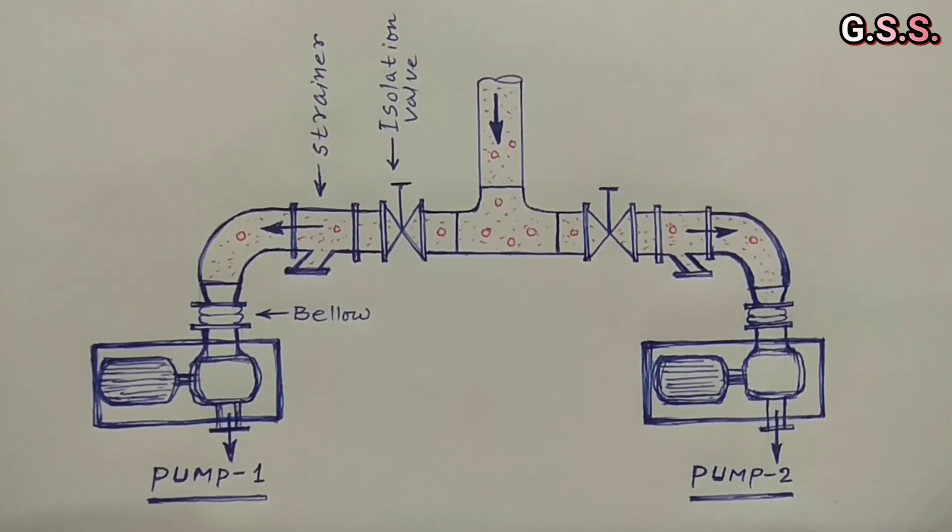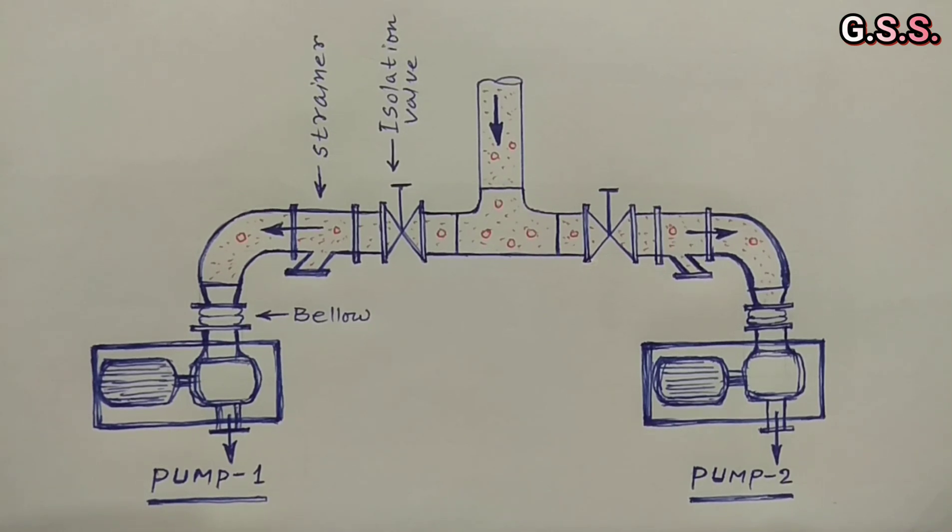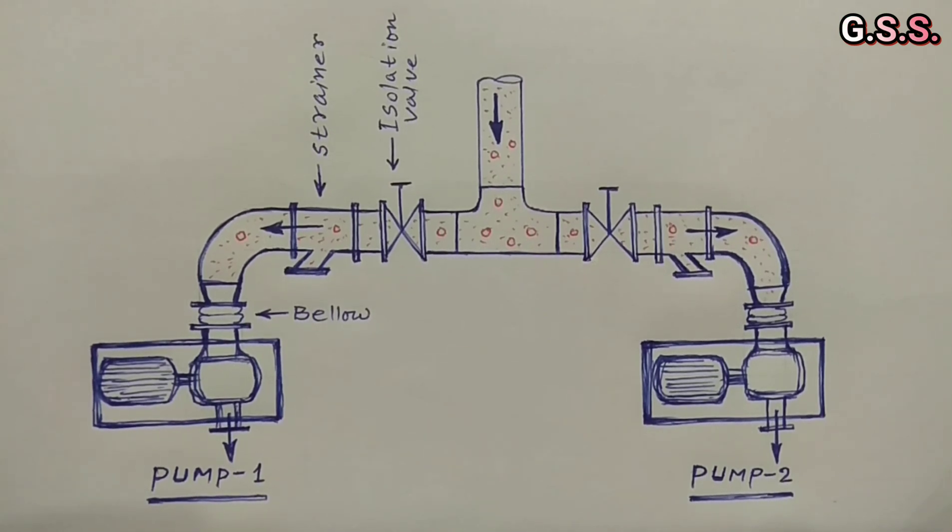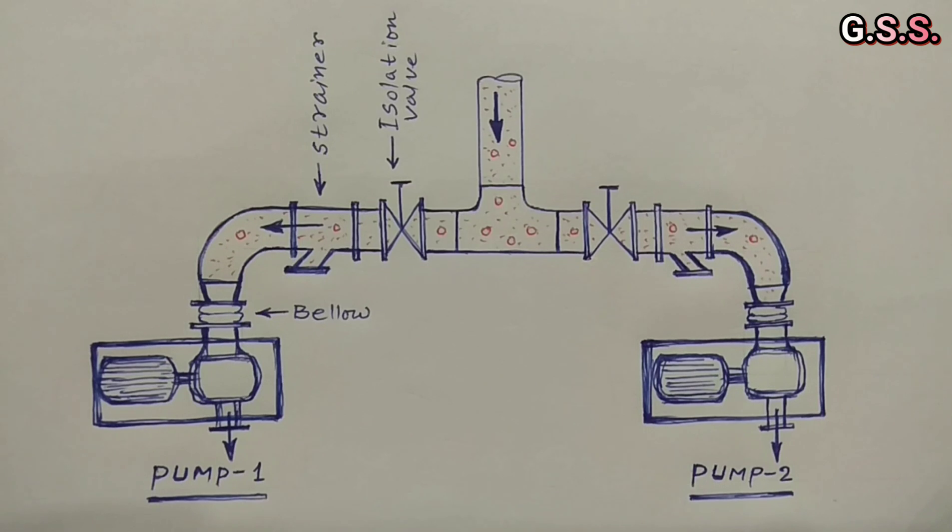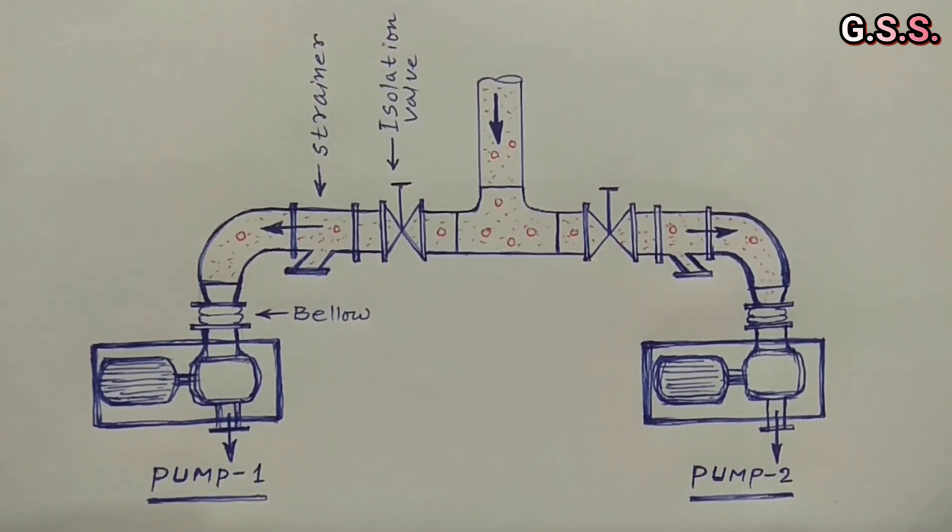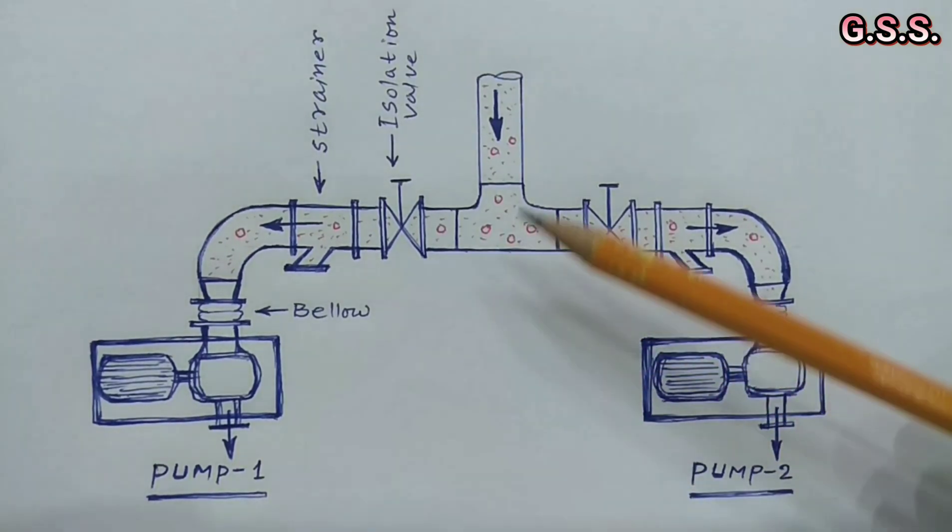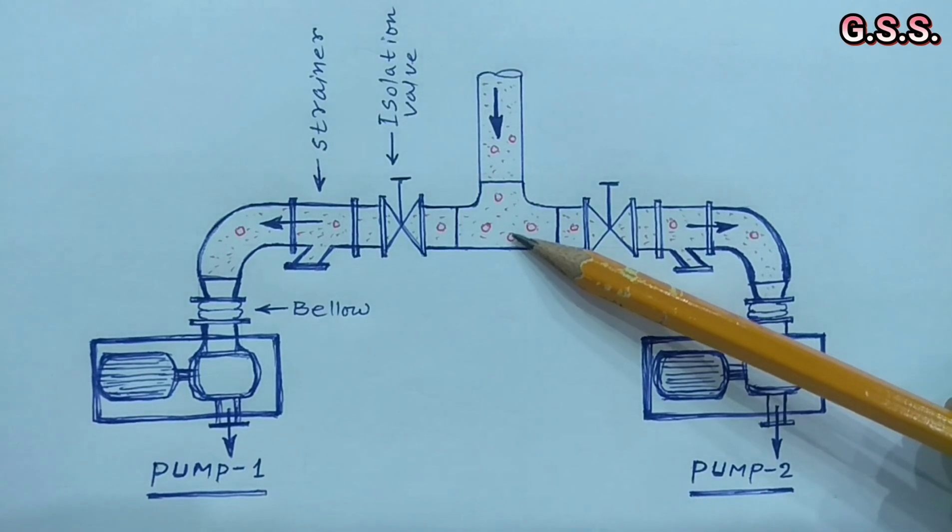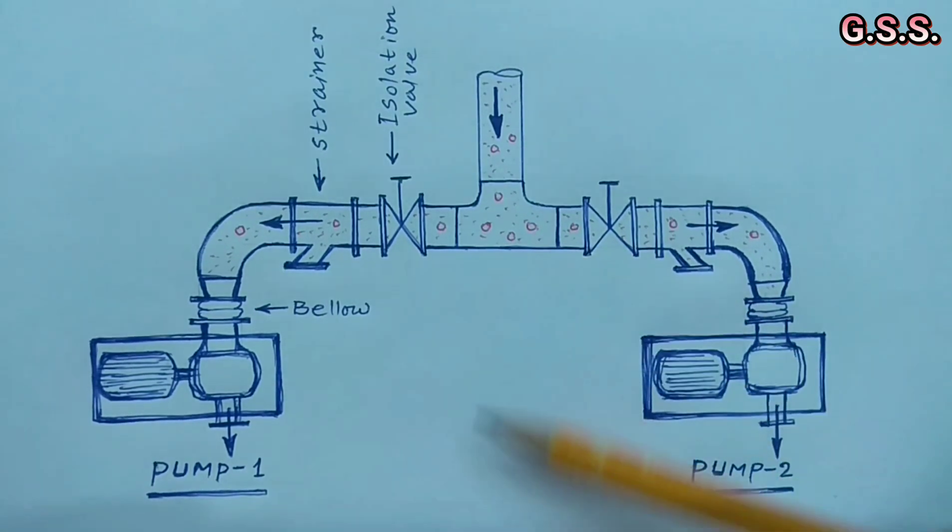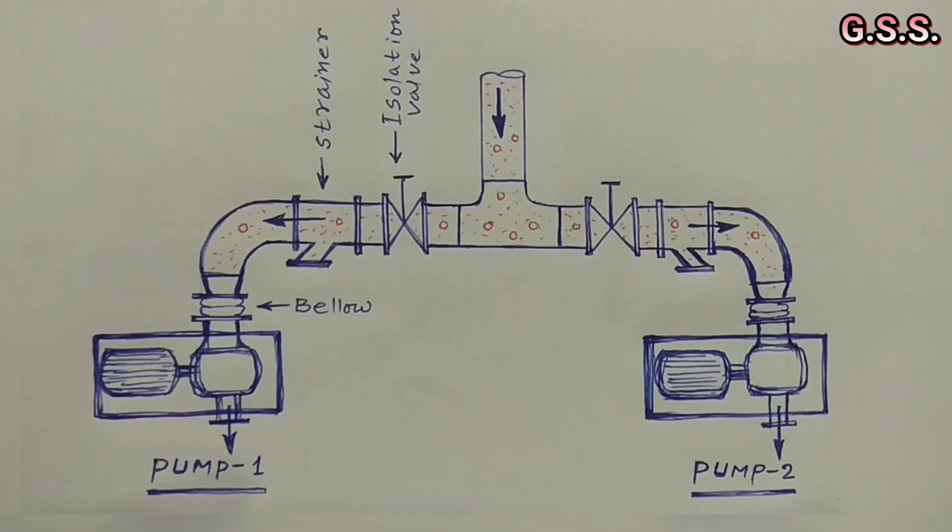When any cryogenic liquid flows, metal of suction line is cooled down and cryogenic liquid generates huge vapor. Cryogenic vapor flows along with cryogenic liquid. Vapor is compressed at this T point and pipeline may vibrate and pressure drop becomes more.